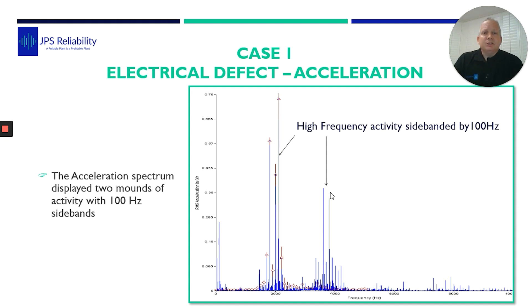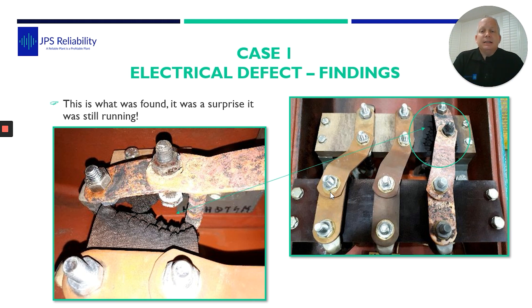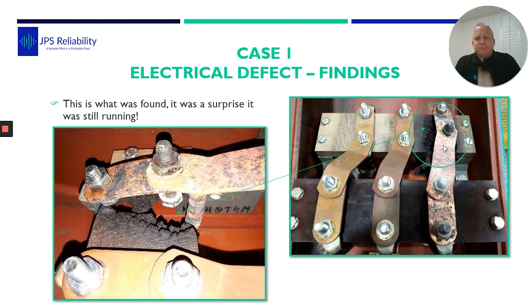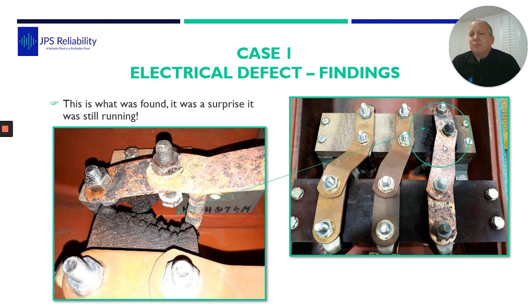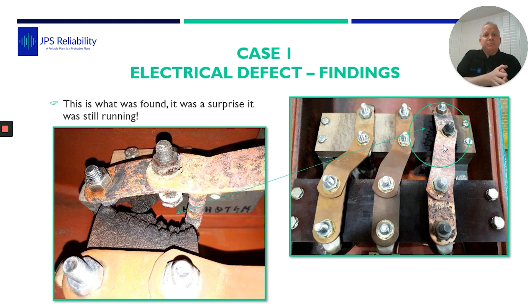Something connection-related. And the recommendation was to check all the terminations. So they took the terminal box off and found one of the phases had got a little hot. I asked them how long the motor had been in — only been in three months. So straight away you think, why did that connection get bad in three months? Now, it was great that vibration picked up this, but you had to use your human senses and a bit of common sense to work out what component was actually causing the issue.